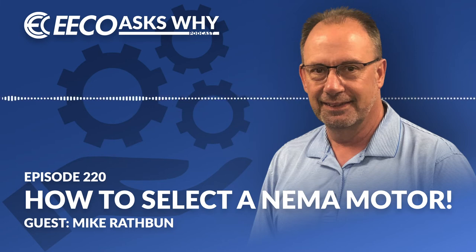Right. And to stay on that path, if a motor fails, should the users out there dig and try to understand why before they just replace it? Well, this speaks to some of our conversations around good reliability practices. What I see commonly in the field is a motor fails in place for whatever reason, and there's an endless list of reasons why that could have occurred. But to just look at the nameplate for that motor and copy it, we don't necessarily know that when that motor had previously failed, it's possible that the exact motor needed for that application was not available in the storeroom, and they chose to use something close. It may not have had the level of protection. Some of these factors were in play when they made that decision last time. Taking a moment to do a little due diligence, why did this motor fail, can ultimately prevent you from going down the same road time after time.